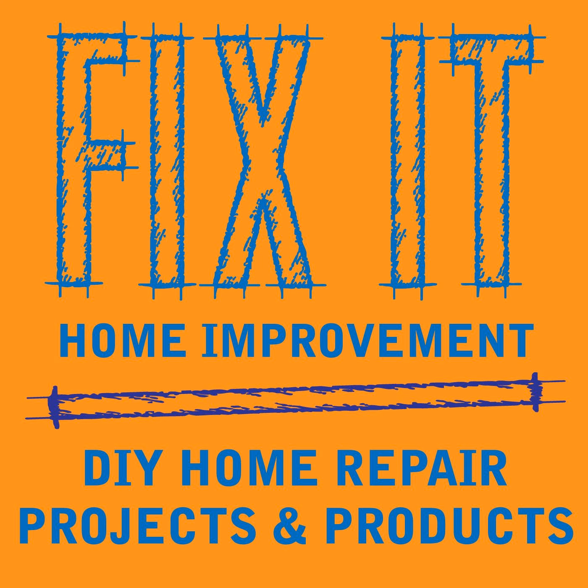So handle with care? Yeah, well, what I would do is get an insulated screwdriver, and as I pull the two leads off, I would touch the two terminals together with the screwdriver, and that's going to discharge the electricity that's built up in it, and then remove the capacitor. You want to match it up, so you want to get the exact same specs because the size... This will all be in your model or your manual? Yes, or on it too. It's going to be marked. And then the size can be different as long as the specifications are the same.